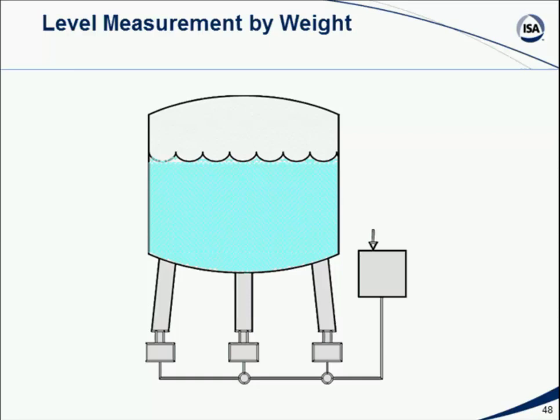Well, if I take a tank and set it onto a set of load cells, so that the legs that support the tank, and here we're showing 3 legs, sit on a set of load cells, and these are devices that as you press down on them harder and harder, their resistance changes, and we can measure their resistance, and by that we can tell how hard you're pressing on them. Well, we've already said that a column of fluid exerts a downward pressure or force, so as the liquid level in this tank goes up, and if we know the density of the liquid in this tank, and we know what the starting weight of the tank is empty, then we can make a measurement of the downward pressure being exerted onto these load cells at the bottom as the fluid level goes up in the tank, and use that to make a rough calculation of the level in the tank.